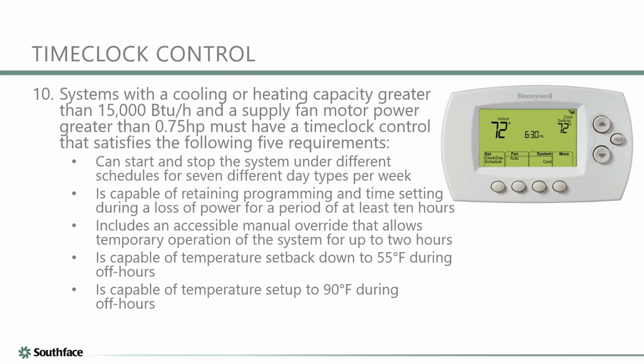So the next one here is another seemingly basic control that's built into thermostats, but again, we have to make sure that it is built into whatever thermostat or control system you're using. So basically, you have these timeclock considerations. First one here, it has to have a 7-day programming window. Older thermostats might have only had basically weekend versus weekday. But to qualify, you really need that 7-day control system.